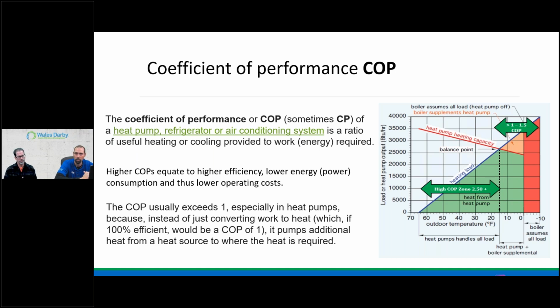So the factors of this, if we have a design day, and let's just say it's 10 degrees, and I want to maintain 70 inside, so there's that spread there, right? But we are never really ever living at zero. It's just in case that we ever do. I want to have enough horsepower to satisfy the space. I get that. But do you think the BTUs for a 0 degree day would be the same when it's only 35 out? Yet the equipment that we're driving, the horse, has no idea what the outdoor temperature is. It just goes off on a stupid air switch and a stupid water switch.